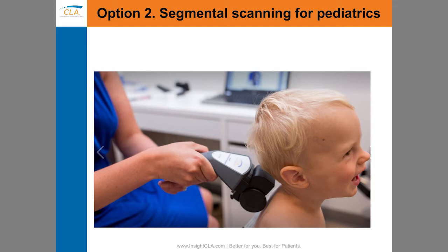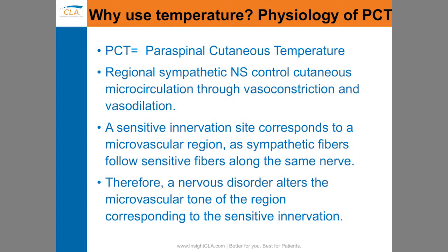I need you to understand that unlike EMG, thermal scanning is used in a non-postural way. So you can have the patient seated. There was a study that was done looking at the differentials between a standing and a prone thermal scanning. They are identical, so you do not need to worry. You can place the patient in a prone position. In babies, many times what we'll do is support that baby over our lap and roll or segmentally scan the segments in that child. And so it's an entirely versatile system for the way in which you can collect that scan.